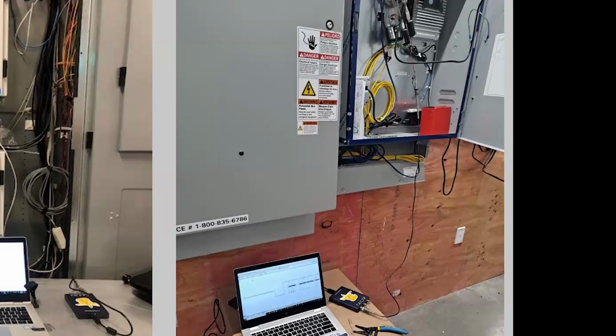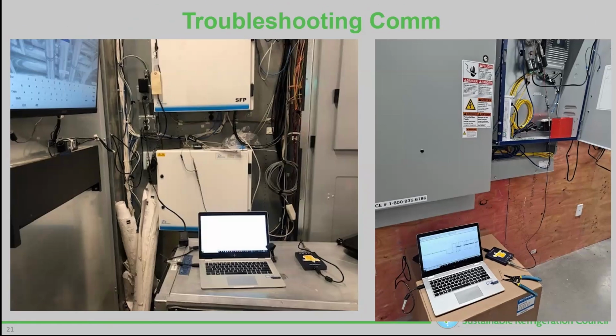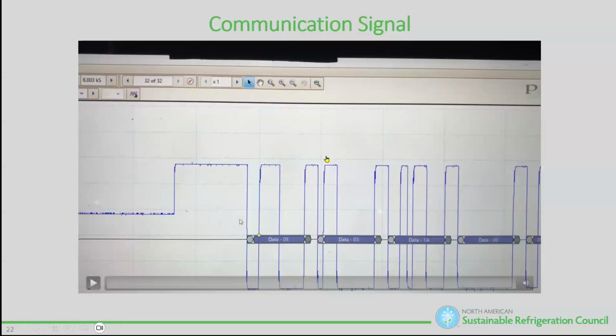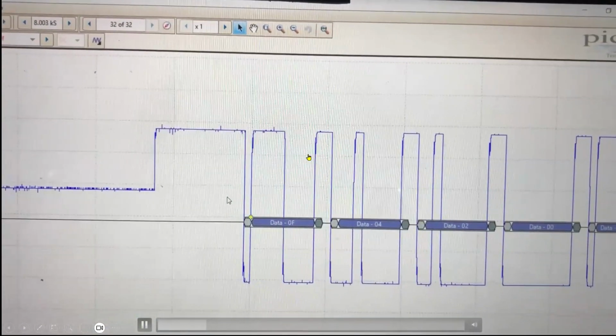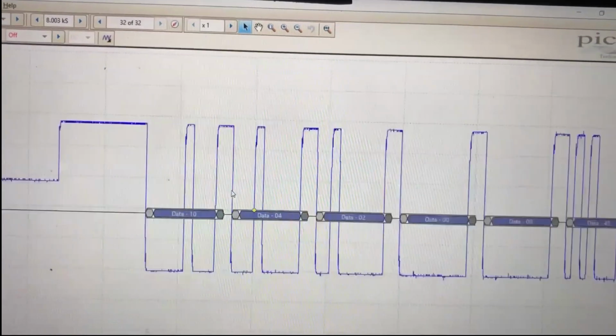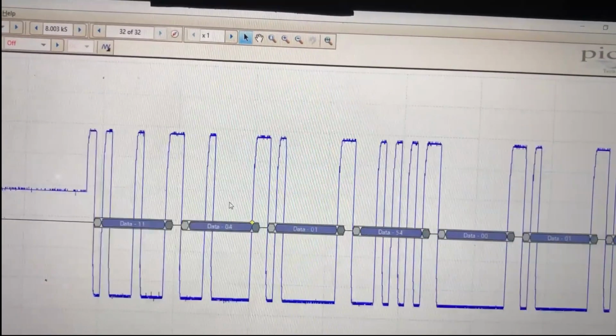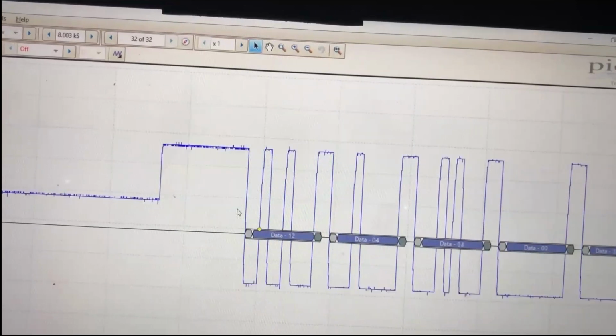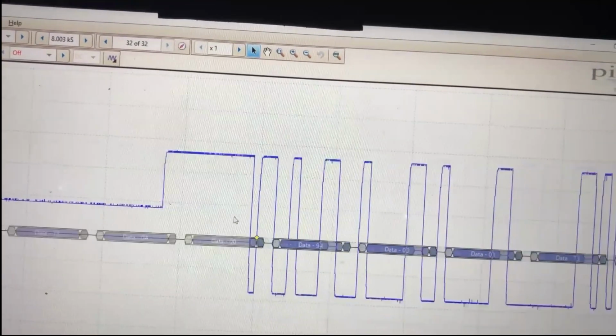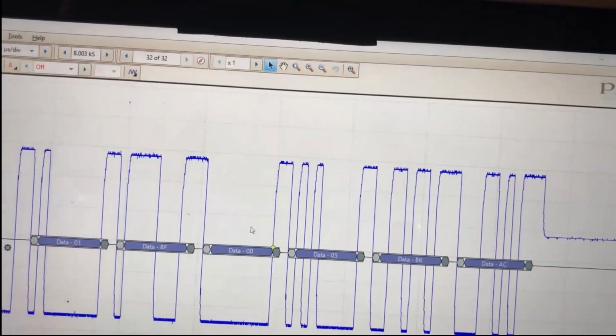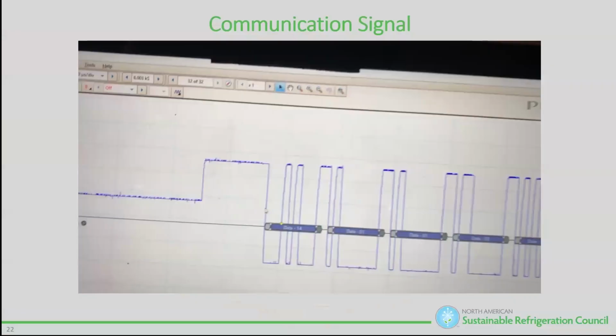What I'm going to do is put my meter leads in parallel with my Modbus signal. If I run this, it's a beautiful square wave. Notice the amplitude, see how it's transmitting. If I hold my laptop up to my controller, where I have that TX and RX light flashing, it'll flash at the same rate. That's a beautiful signal.